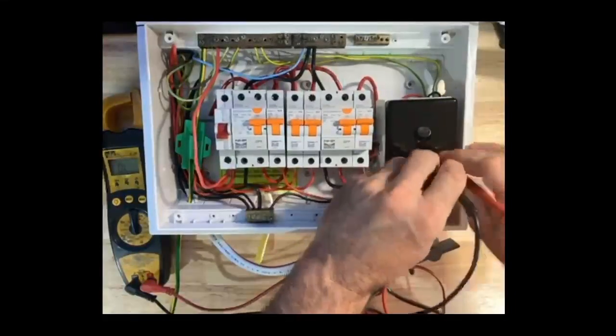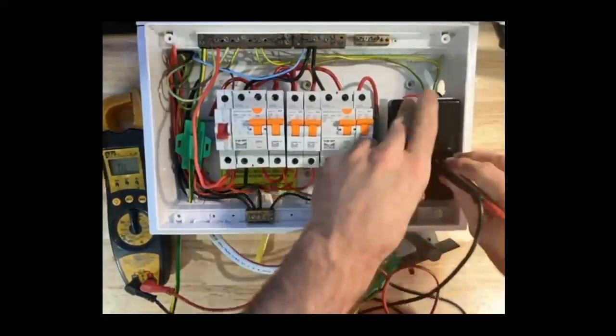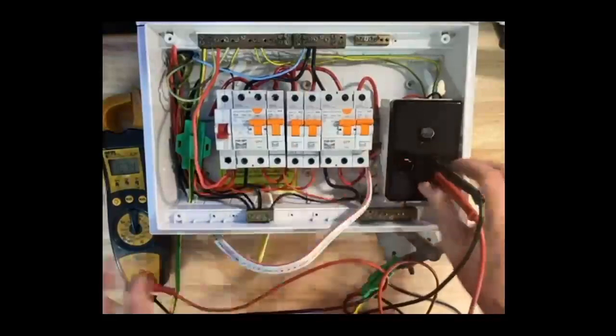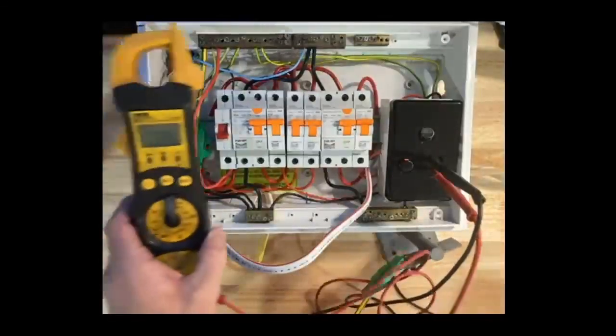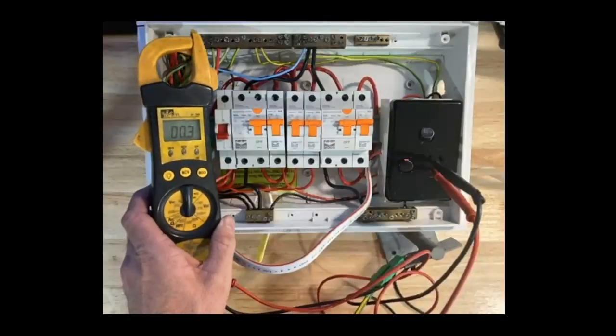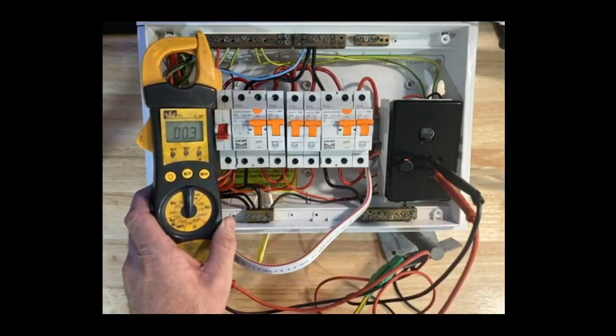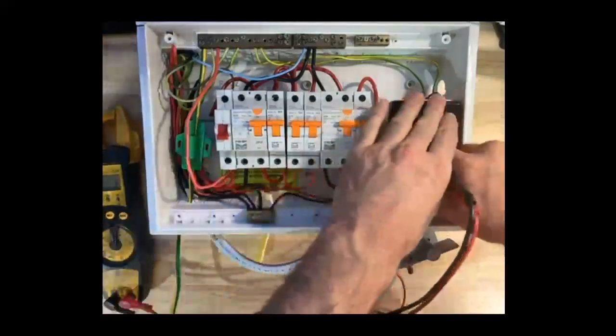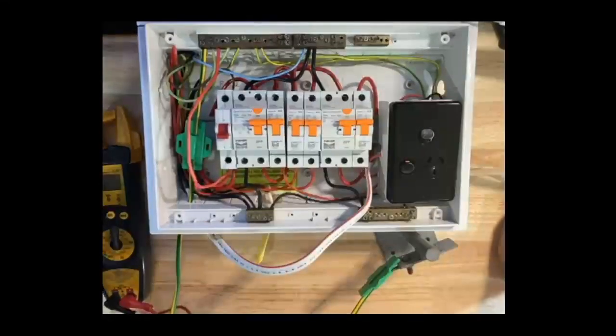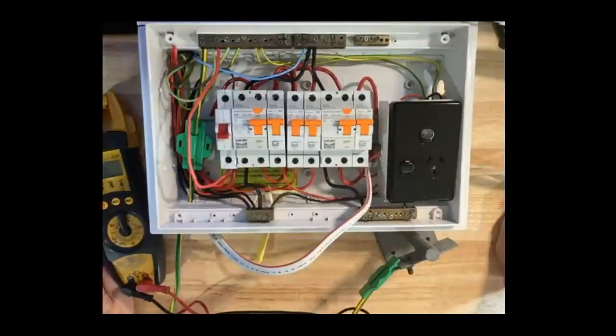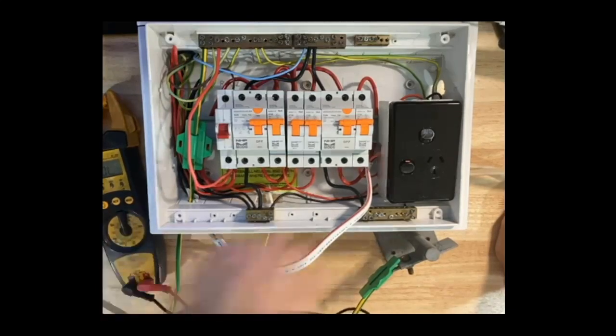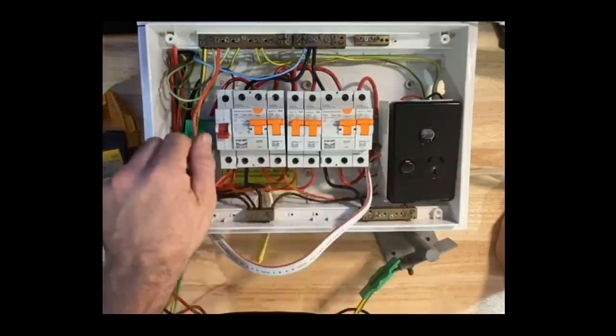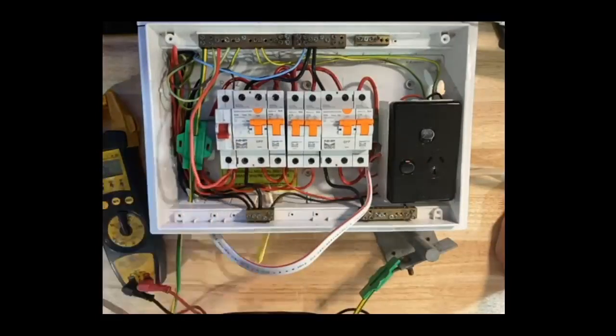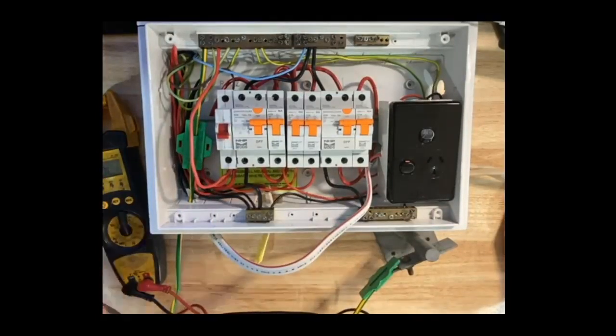Oh, I have to go into the neutral first to open the shutter, which will allow me to connect to the phase, and then I can go to the earth. And you can see on my meter there, I've got a reading of 0.3. Oh, it's fantastic. Now you can imagine if I was doing this earth continuity testing throughout an installation, there may be many sockets, 20, 30, 40 sockets, and probably as many lighting points and various other items of electrical equipment. So this could be quite a time-consuming test to go all around the house and do this. And this little connection here allows me to do this much, much more easily.